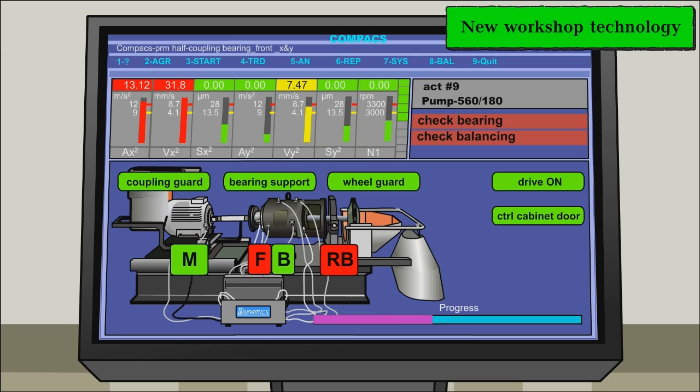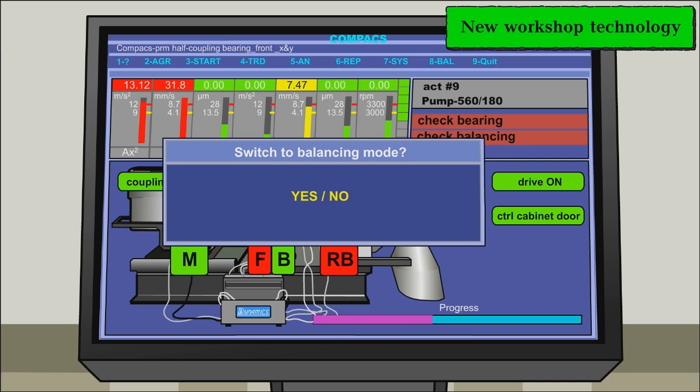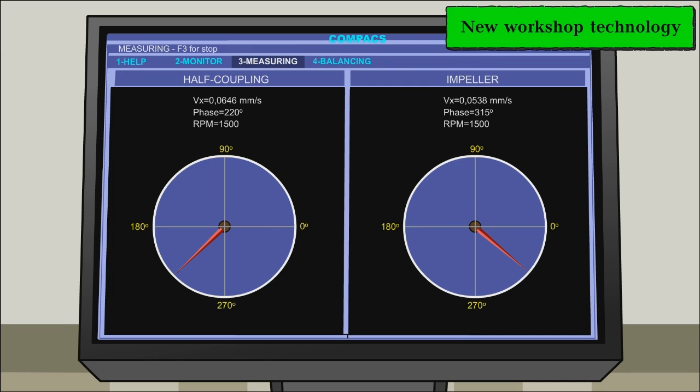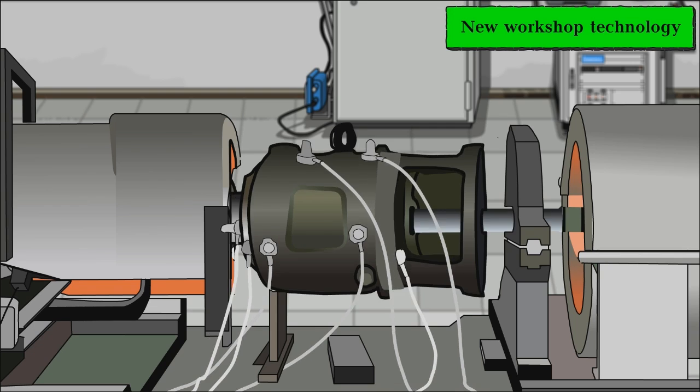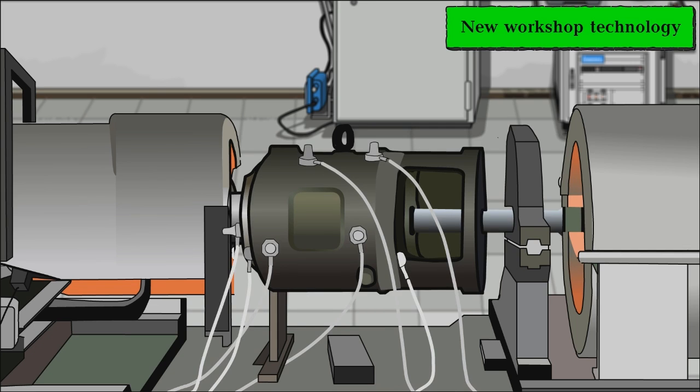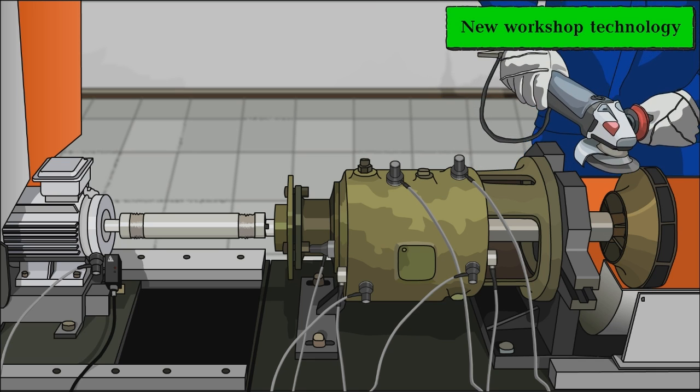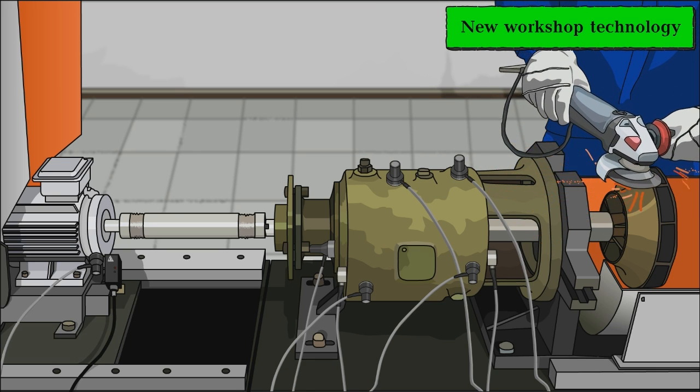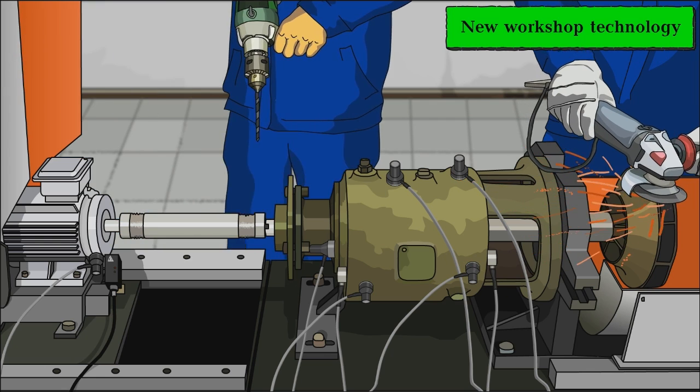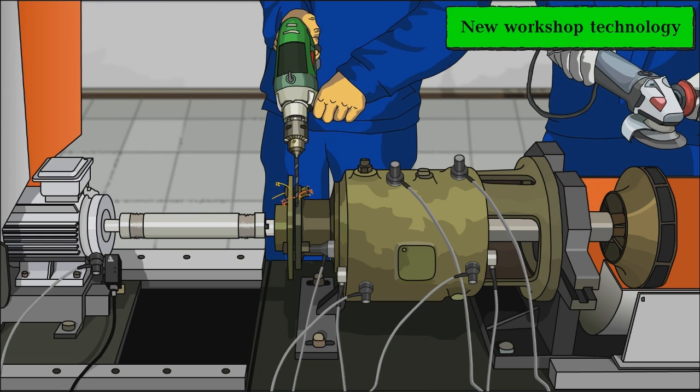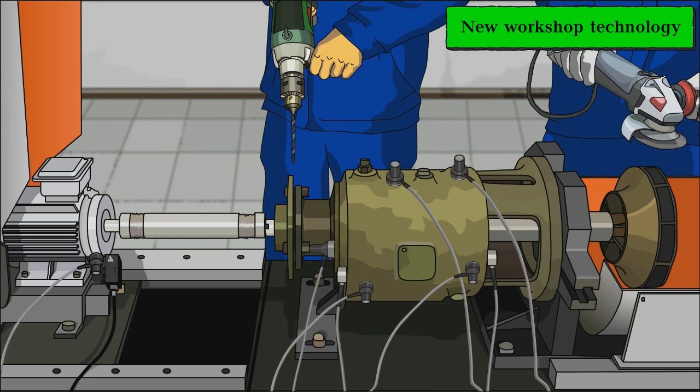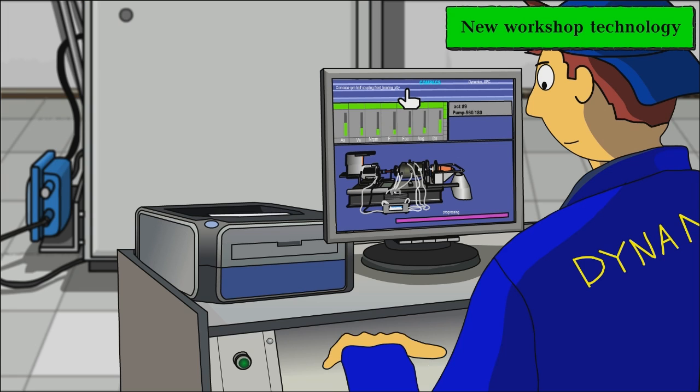The system automatically shows the angle and value of the unbalance, both from the impeller and half-coupling sides. Due to the high precision of the unbalance detection, balancing is usually carried out at the first start-up.